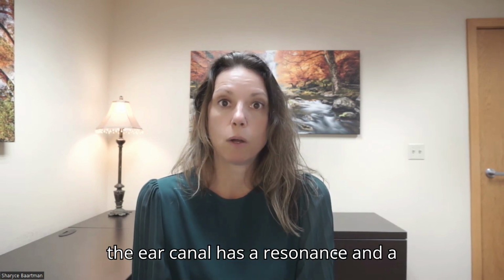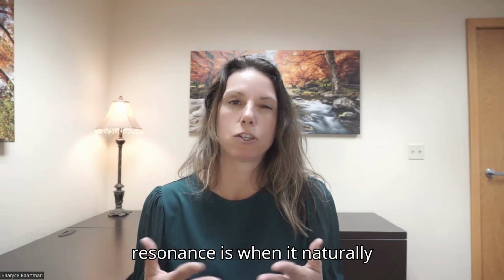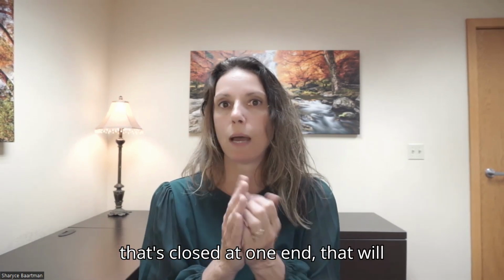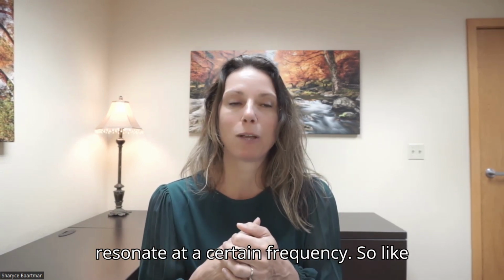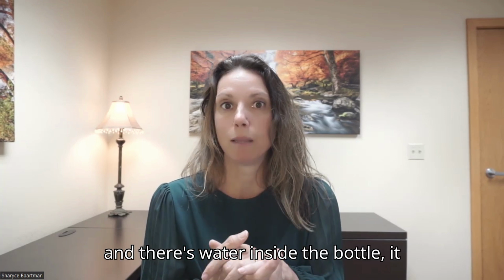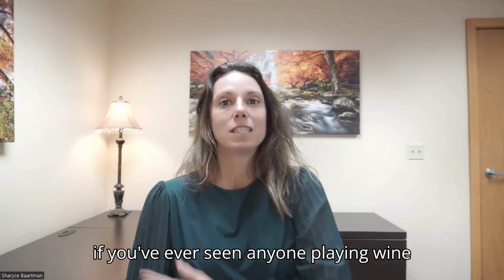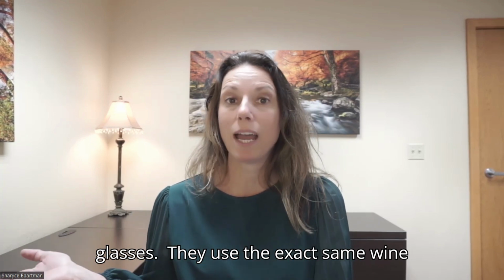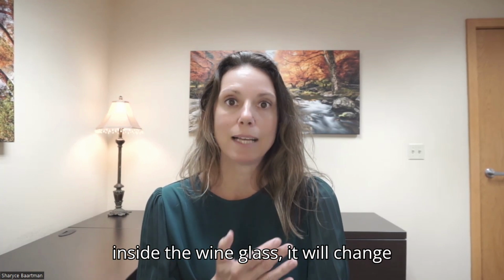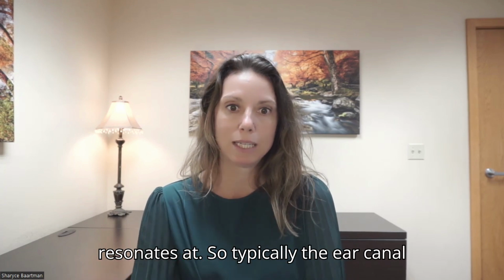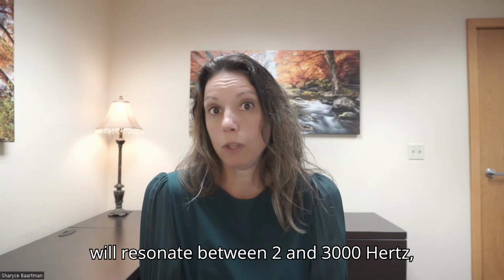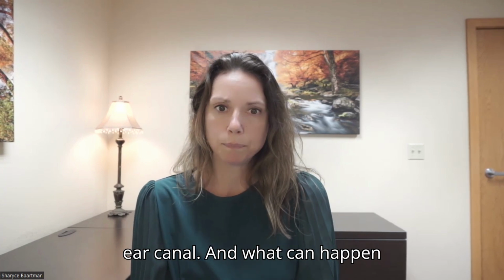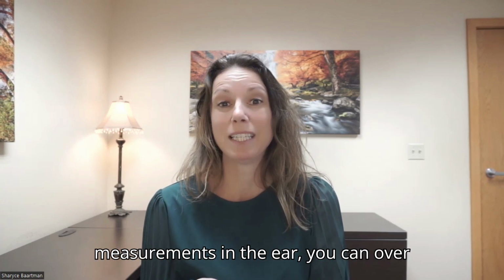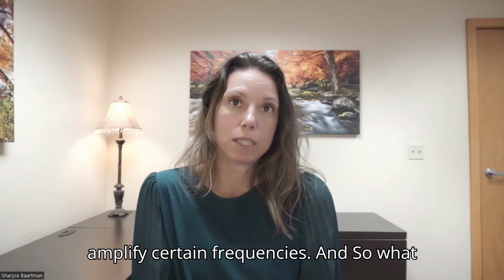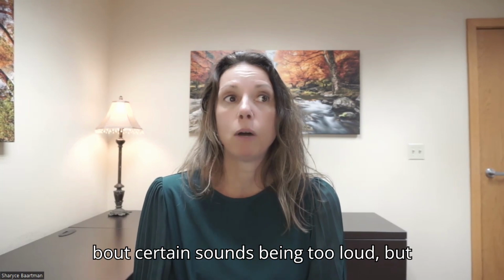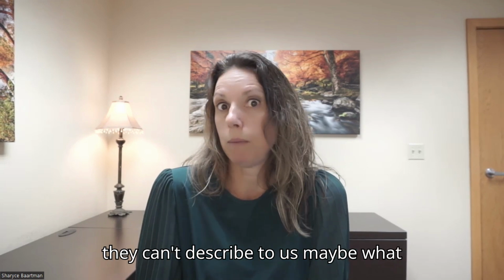The other thing is the ear canal has a resonance, and a resonance is when it naturally amplifies sound. Anytime you have a tube that's closed at one end, it will resonate at a certain frequency. Like when you blow across the top of a bottle with water inside, it will resonate at a certain frequency. Or if you've ever seen anyone playing wine glasses, they use the exact same wine glass, but depending on how much liquid is inside, it changes the frequency it resonates at. Typically the ear canal will resonate between 2 and 3,000 hertz, depending on the length of the person's ear canal. If we're not doing measurements in the ear, you can over amplify certain frequencies. People might complain about certain sounds being too loud, but they can't describe to us what those sounds are.